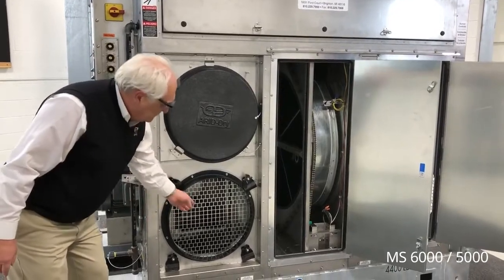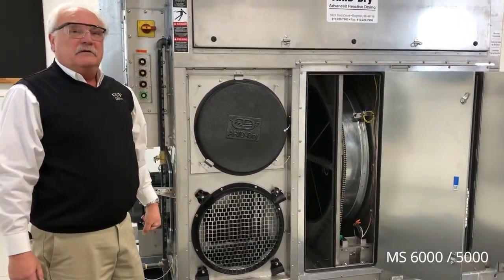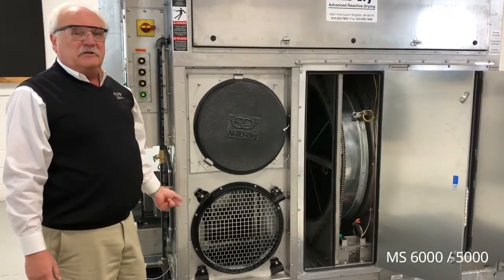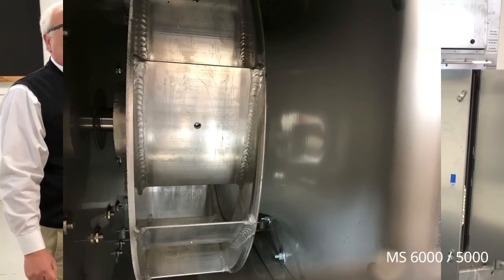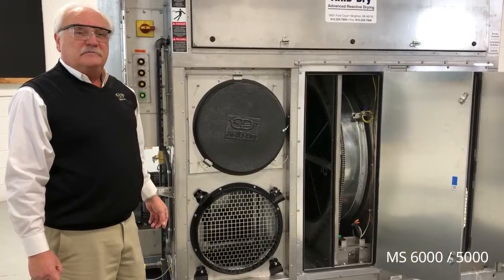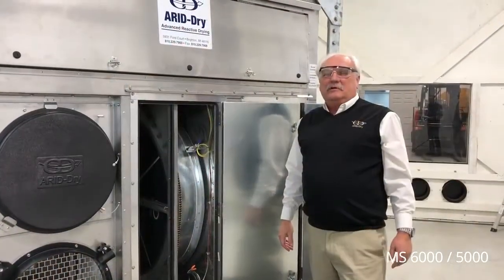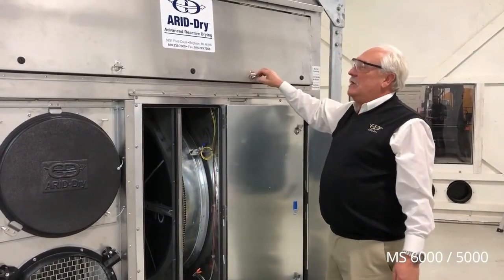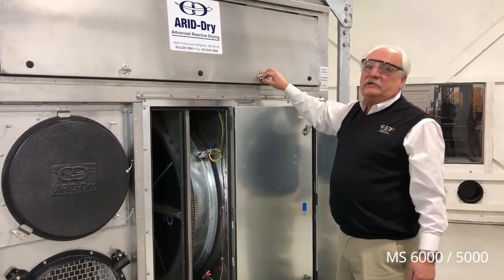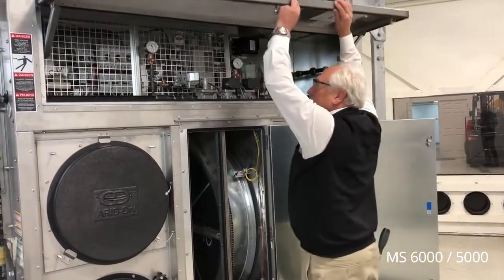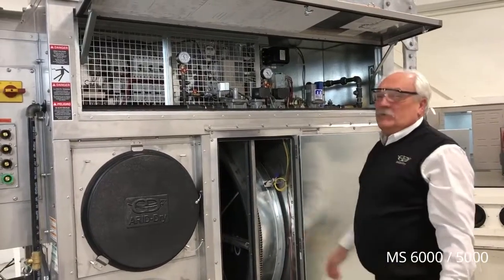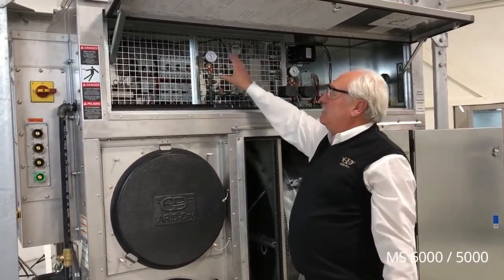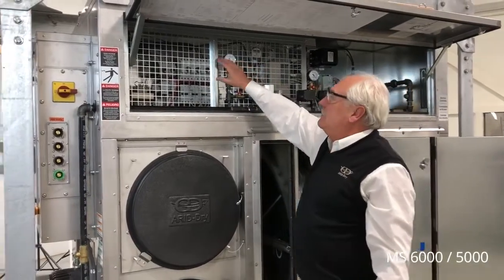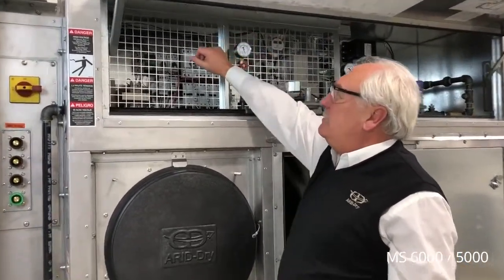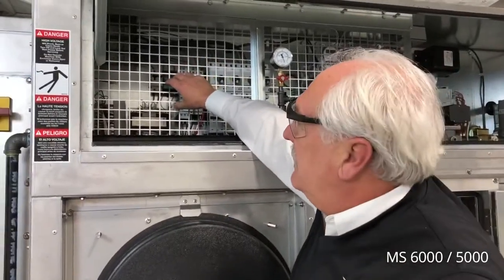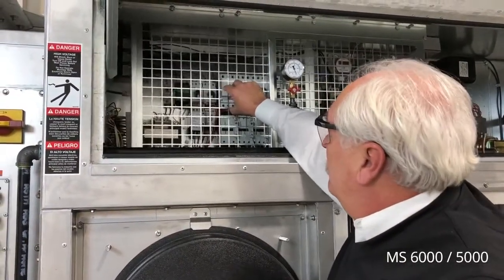The blower is located inside behind the finger-safe screen. This blower is capable of up to 5 inches of external static pressure, approximately 9.6 inches of total static pressure. Above the desiccant wheel access door is our high voltage electrical panel and gas train compartment. On this side, you'll see our finger-safe guards so that it's protected while the guards are in place. If service is required, the guards can be moved to allow access to the high voltage components.